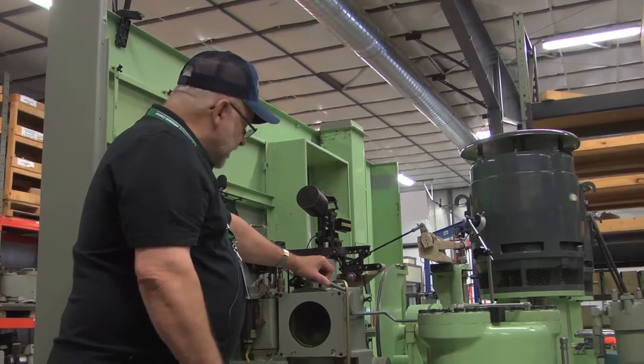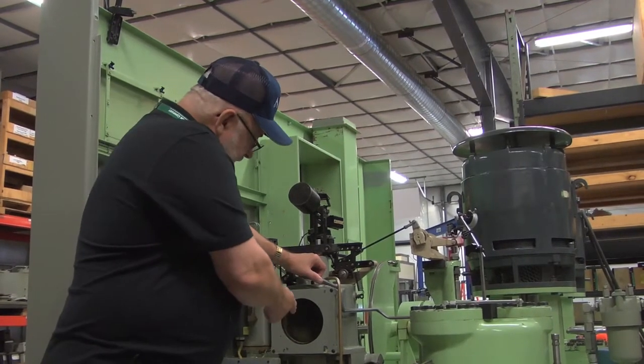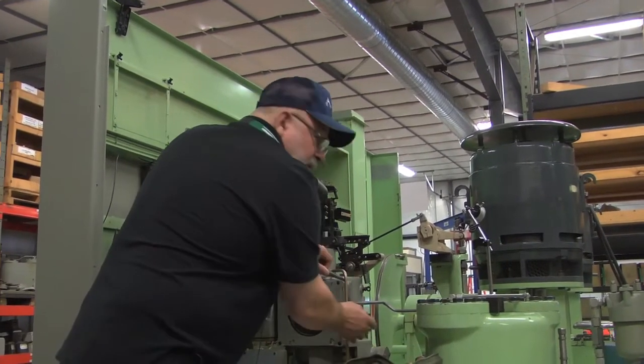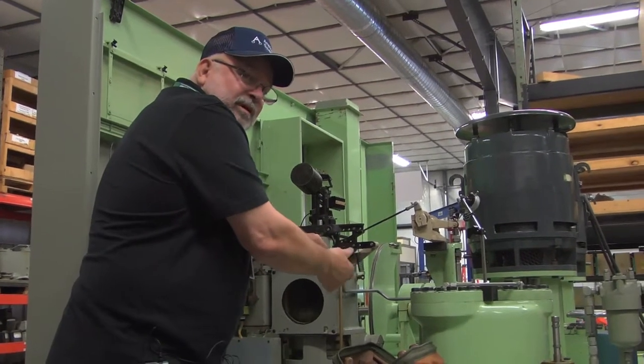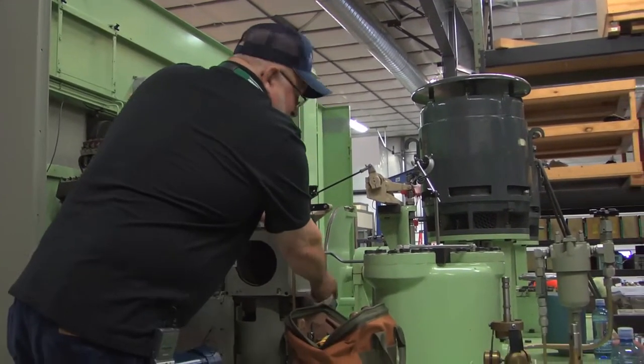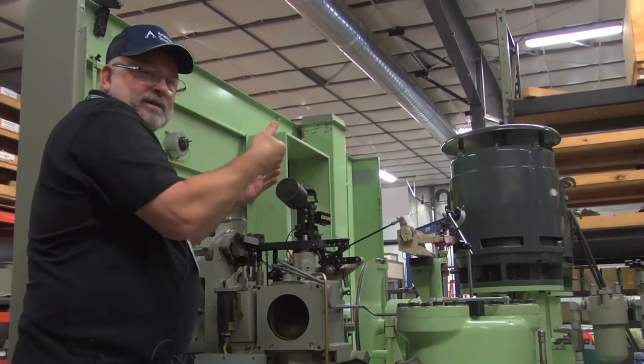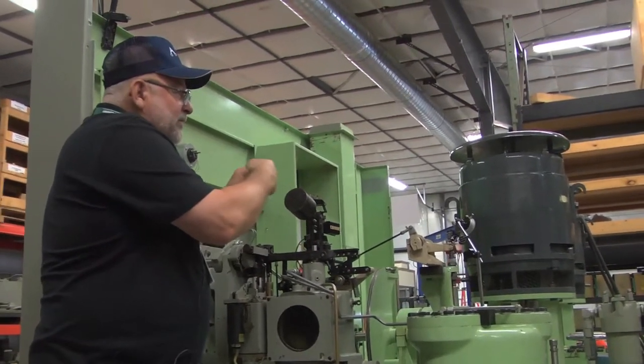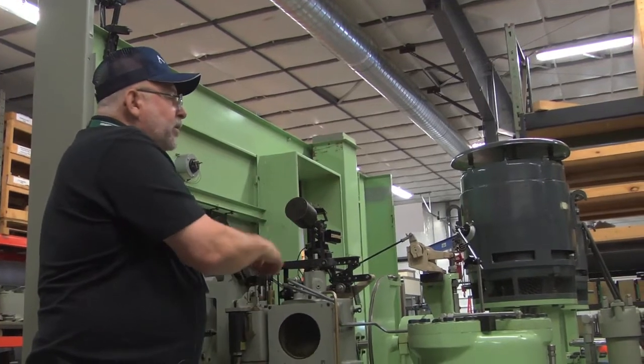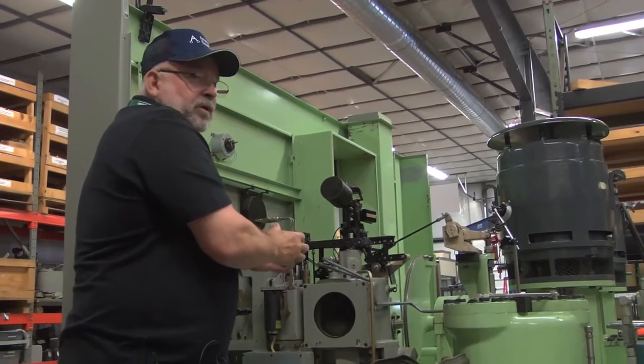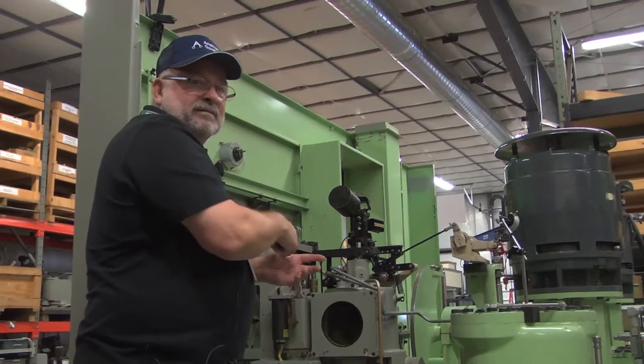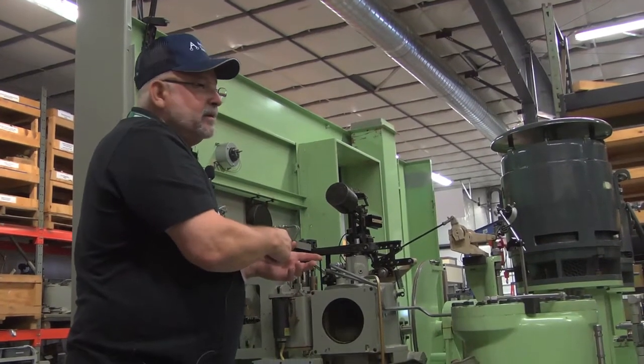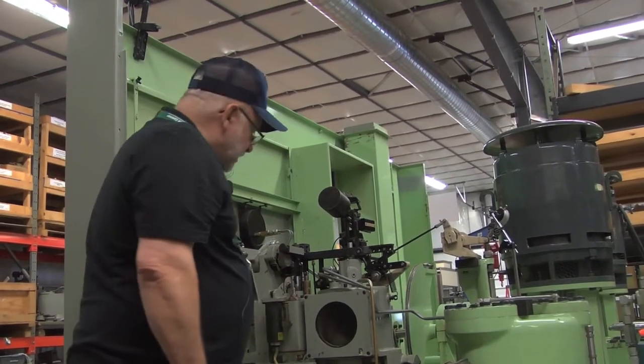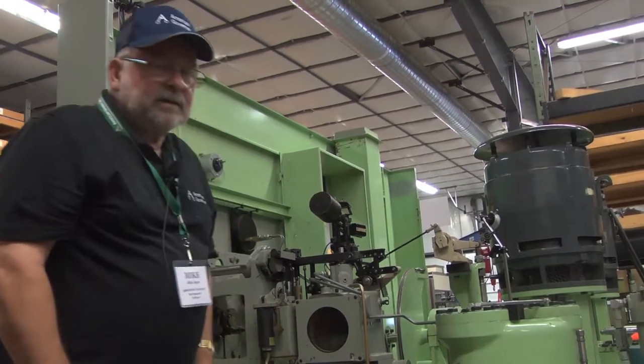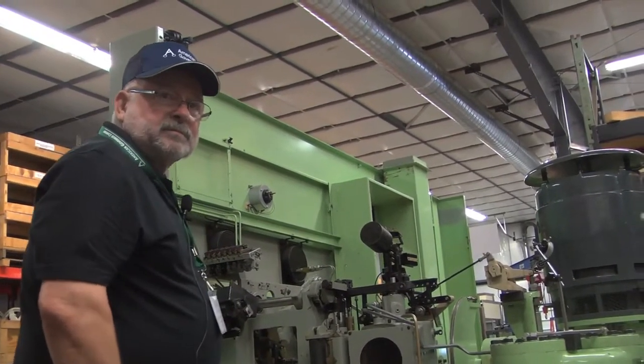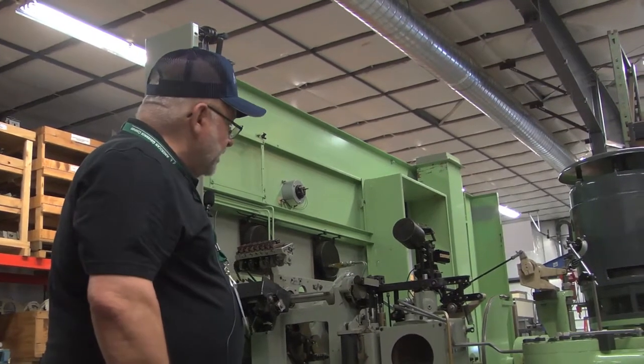They had been down. And the reason they get down is because when they take this apart to change the bearings and drop the motor out sometimes, somebody dinged up this drain, the way it goes in there, it has O-rings in it. Well, they left some rings out, and that oil was running down in the motor, and when the motor shorted out and burnt the motor up, it sucked that magnetism out of the PMG. Bill's talked about remagnetizing stuff. The electricians do a lot of stuff I don't even know what they do.